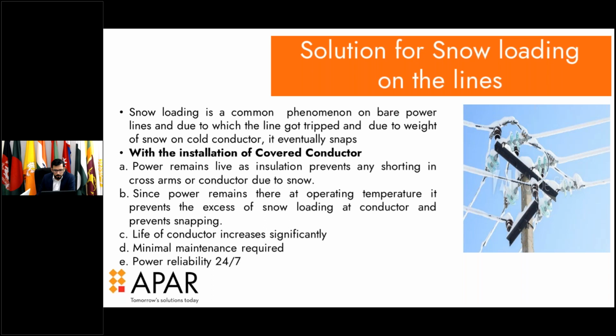Also, covered conductors were invented in Scandinavia, a very cold region. Their observation was that during snowfall, snow loading accumulates on conductors and cross arms, and when short circuiting takes place, the line becomes cold. Once it becomes cold, more snow deposits on the surface, increasing the snow loading, and eventually the conductor snaps. In some of our northern areas with heavy snow, every year they have to change the bare conductors after the snow period because they snap. One benefit of the insulation in covered conductors is that the line never becomes cold because there's no effect of short circuiting.